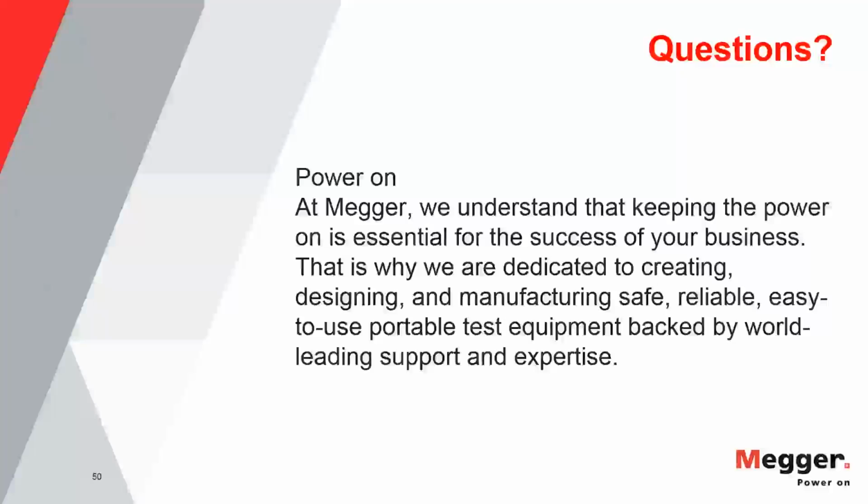This is Robert, and just to add to this, keep in mind that the main reason why the VLF technology was invented was because the DC hipot was not available anymore. So this is a tool to replace your standard commissioning test and maintenance test withstand. And the cosine rectangular has naturally a much higher test capacitance than a sinusoidal test set because of the physics involved. Now the DAC is mainly a PD diagnostics waveform.